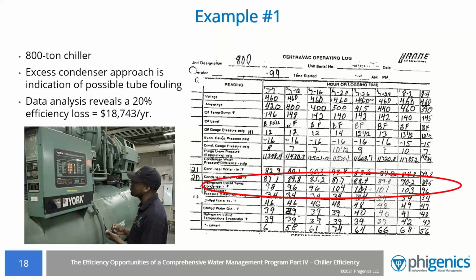And if you look closely at this log sheet, you'll see that down in the condenser section, they're running approaches of 10 or 11 degrees on the condenser, if not higher, on a chiller that should have about a 1 or 2 degree approach at full load. And what that indicates is about a 20% efficiency loss. And for the way this chiller operates and their load analysis, it's probably costing them in the order of $18,000 to $20,000 per year per chiller for a problem that, number one, is easily identifiable if you look at the log sheet properly and do the right calculations. So the point I'm trying to make here is that collecting data by itself doesn't get the job done. You have to have a process for analyzing the data to get the results that you need. Next slide, please.